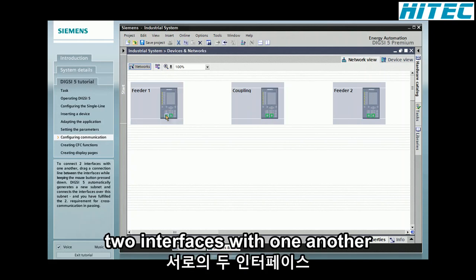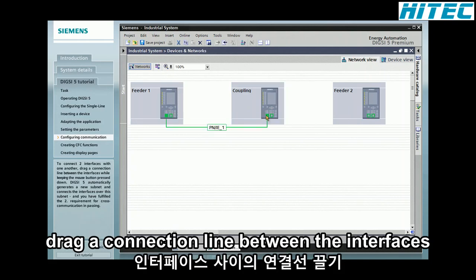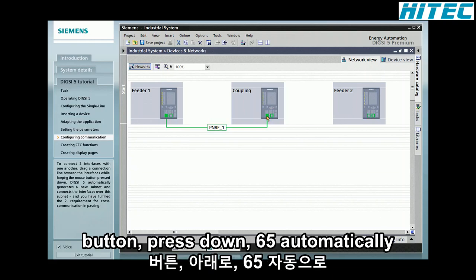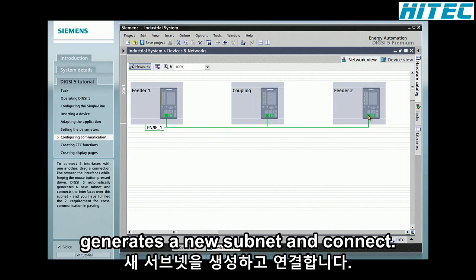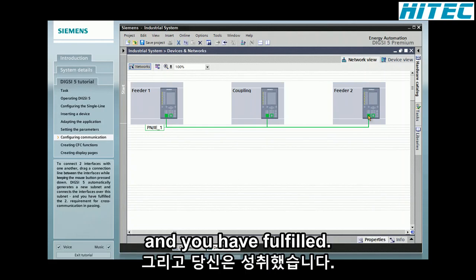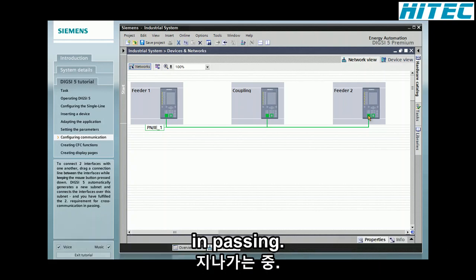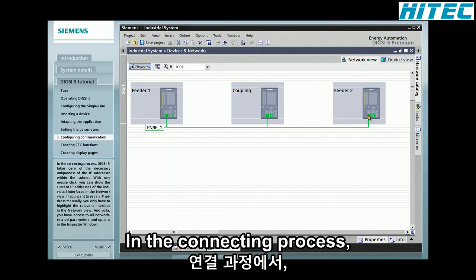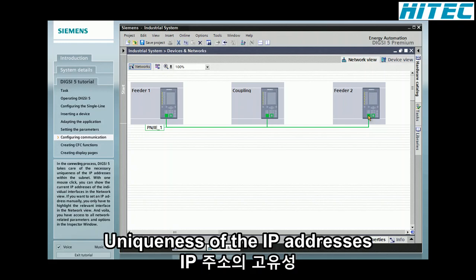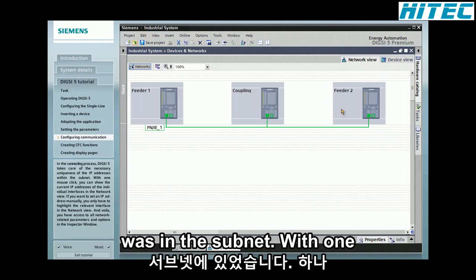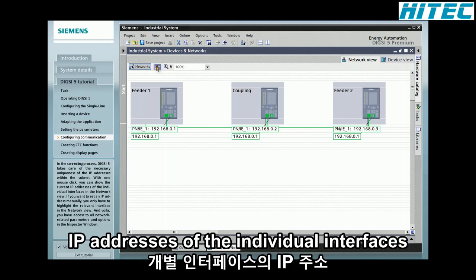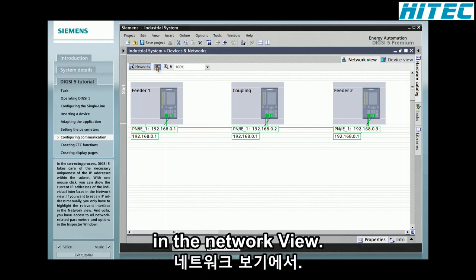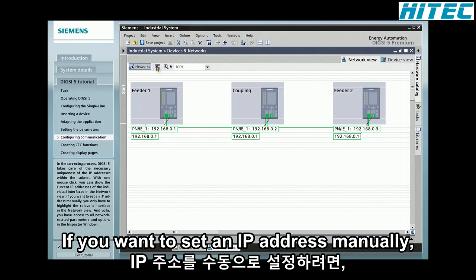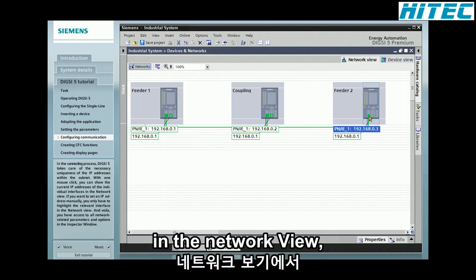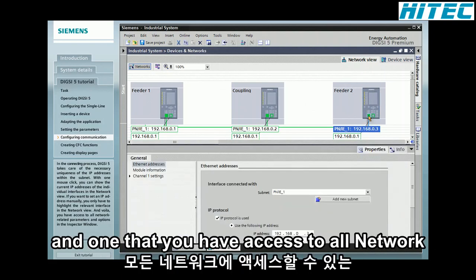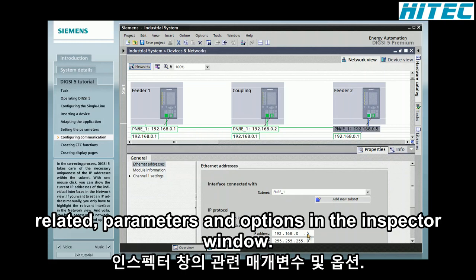To connect two interfaces with one another, drag a connection line between the interfaces while keeping the mouse button pressed down. DIGSI 5 automatically generates a new subnet and connects the interfaces over the subnet, and you have fulfilled the second requirement for cross-communication in passing. In the connecting process, DIGSI 5 takes care of the necessary uniqueness of the IP addresses within the subnet. With one mouse click, you can show the current IP addresses of the individual interfaces in the network view. If you want to set an IP address manually, you only have to highlight the relevant interface in the network view. And voila, you have access to all network-related parameters and options in the inspector window.